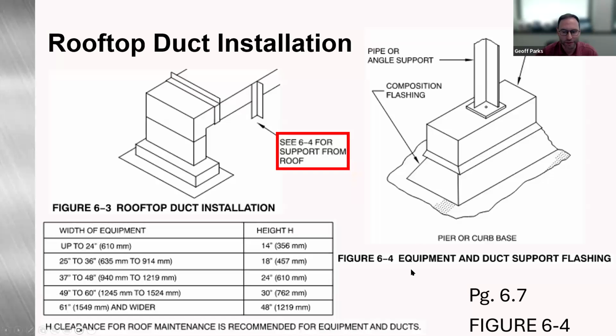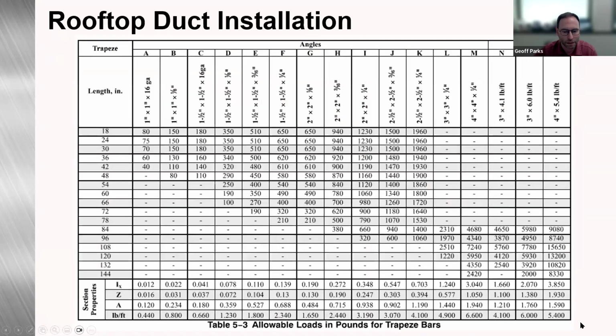Within this page 6.7, there's some recommended roof clearances for maintenance for equipment and ductwork. Up to 24-inch would be a 14-inch height, all the way up to 61 and wider. You're looking at about 4 foot off of that roof for clearance purposes. Since we were discussing rooftop duct installation, obviously, if you have quite large ductwork, you're going to size your trapeze bar the same way that you would size it if you were supporting the ductwork within the building.